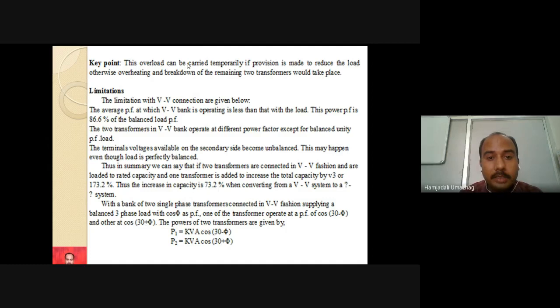Now, this overload can be tolerated temporarily if provision is made to reduce the load, otherwise overheating and breakdown of the remaining two transformers would take place. So make sure that this load is not there for a long duration, because each transformer's own capacity is to carry 100% load. If you make the other two transformers carry the load for a long duration, there is every possibility that they may get overloaded. That overloading may cause heating, and overheating may cause breakdown of the remaining two transformers also. So whenever we are operating the VV connection, don't allow a large load to operate for a long duration. Only for a short duration can we operate the transformers very safely.